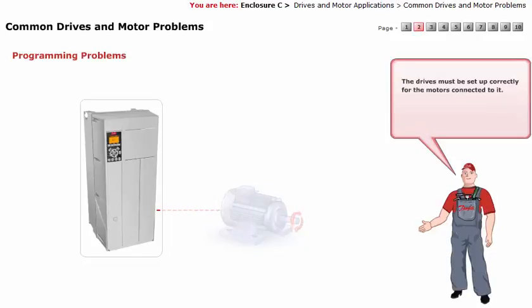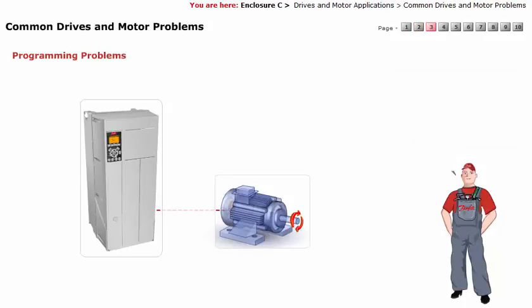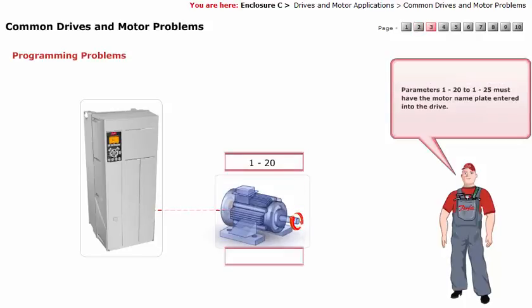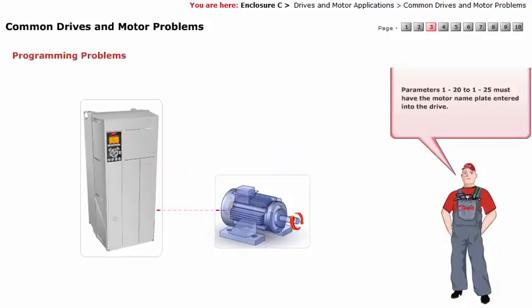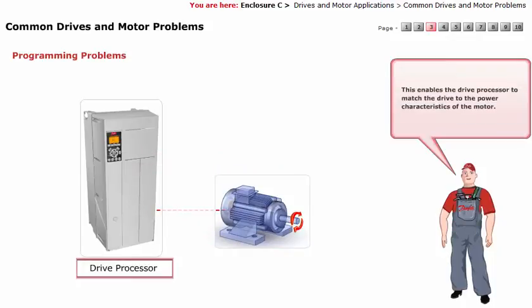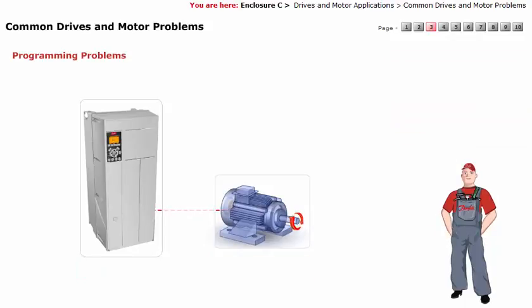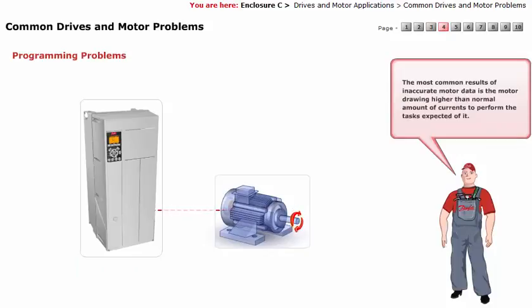The drives must be set up correctly for the motors connected to it. Parameters 1-20 to 1-25 must have the motor nameplate data entered into the drive. This enables the drive processor to match the drive to the power characteristics of the motor. The most common result of inaccurate motor data is the motor drawing a higher than normal amount of current to perform the task expected of it.